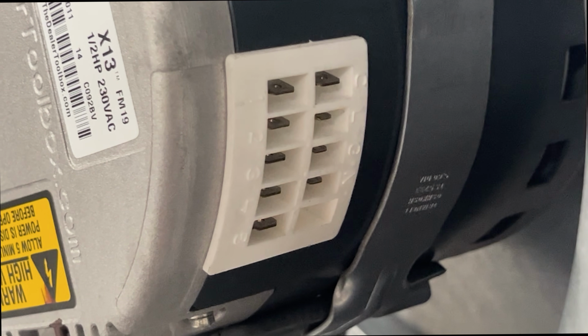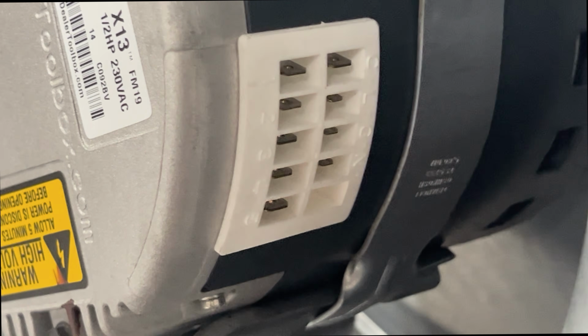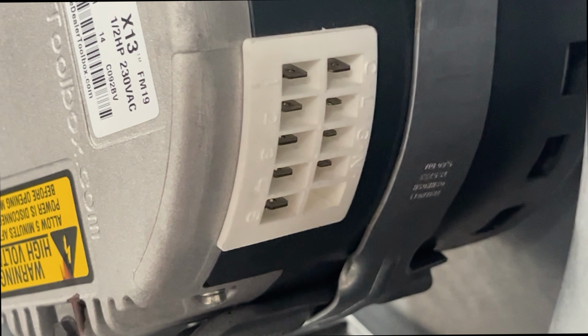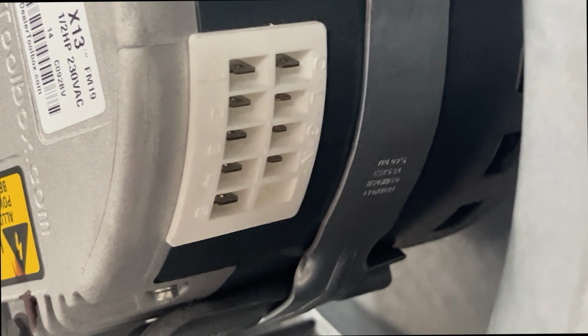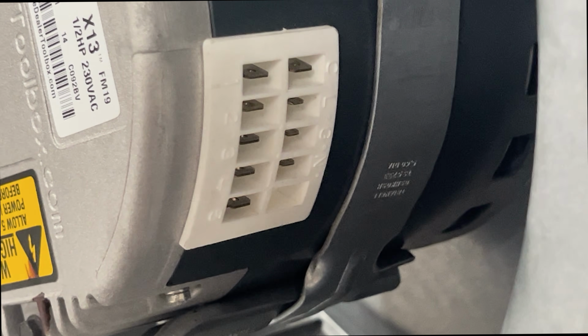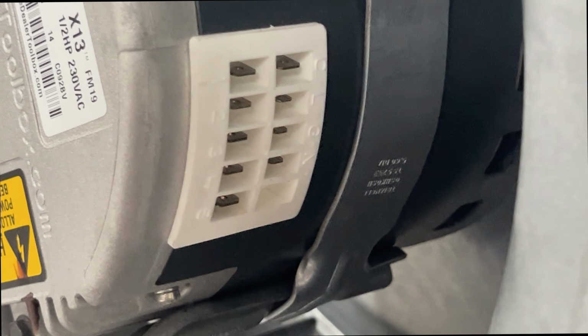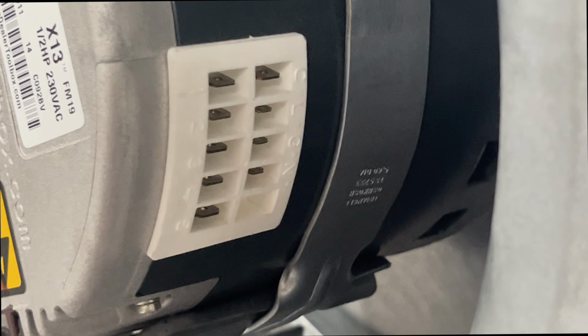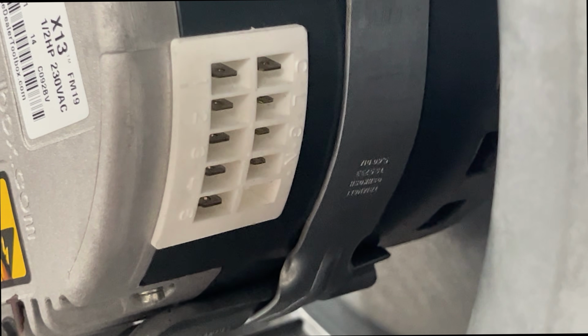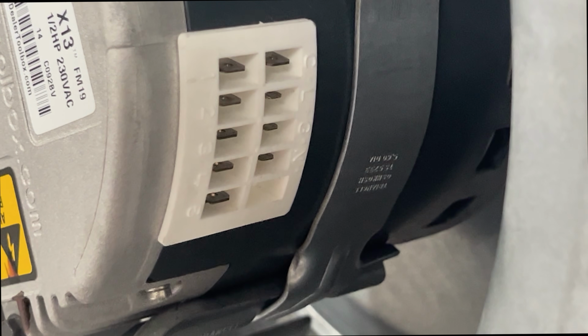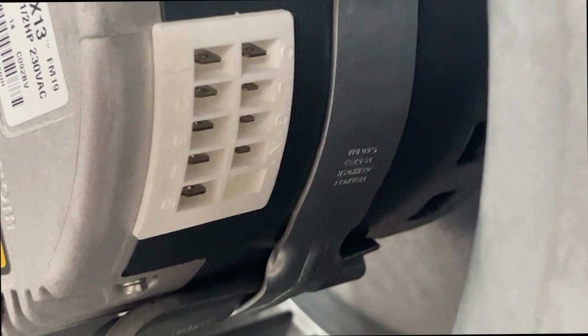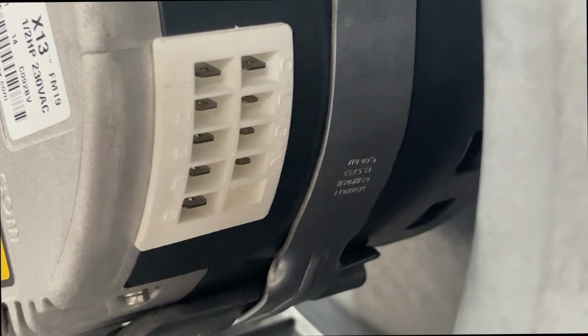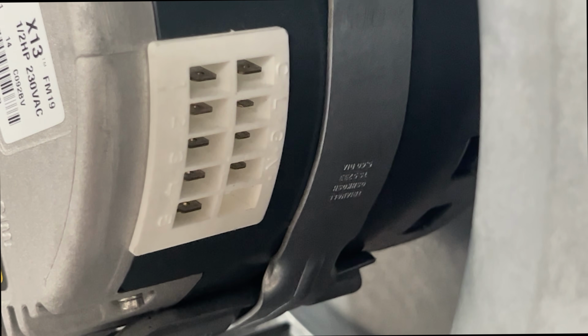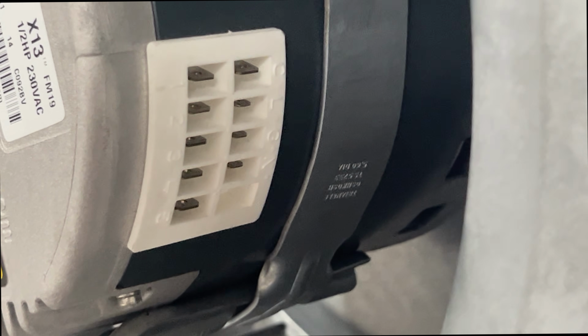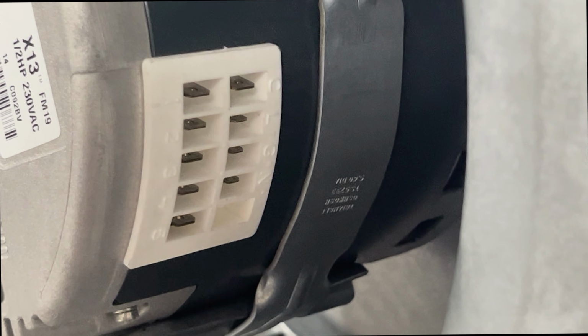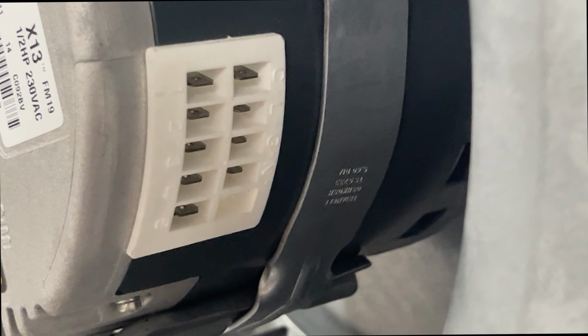The reason why you're hooking 2 speeds up at a time is because if the heat strips are running, or if you have a second stage running, the motor needs to be pushing more airflow across either the heater element in conjunction with that evaporator coil if it's a heat pump. That way you don't cause any issues with the equipment malfunctioning because of the high head pressure or whatnot, or too much temperature in your supply air plenum. And so you have to have more airflow for that.